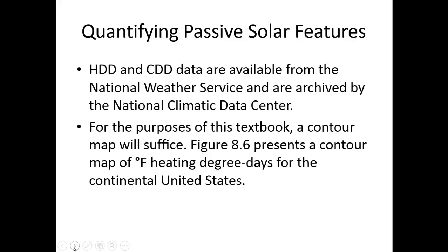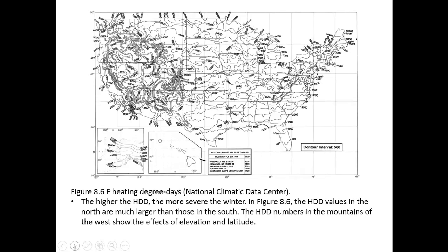Cooling degree day and heating degree day data are available from the National Weather Service and archived by the National Climatic Data Center. For this course, Figure 8-6 in your text presents a contour map of degree Fahrenheit heating degree days for the continental U.S. In Florida the contour level is around 500, while values approach 10,000 up in the north. The higher the heating degree day value, the more severe the weather; the mountains of the west also show the effects of elevation and latitude.